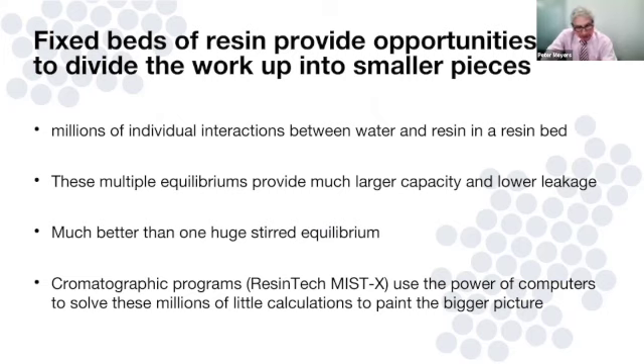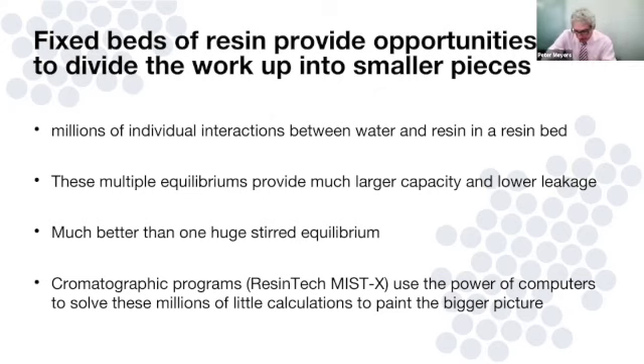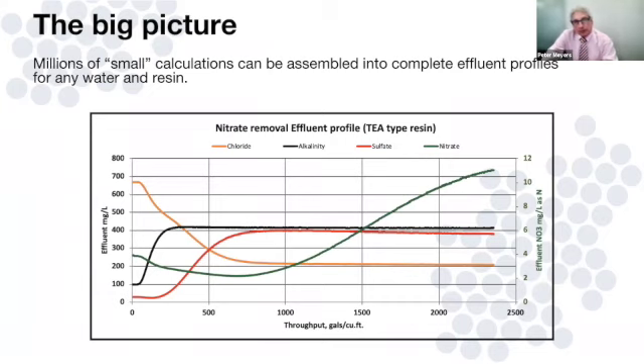There are about 5,000 resin beads in one milliliter of resin, and every one of those beads is interacting with the water separately. By doing millions of individual calculations we can compile a bigger picture that includes higher capacity and lower leakage — much better than a big stirred equilibrium. The same applies in regeneration; you can't regenerate effectively just by mixing resin with chemical. Chromatographic programs like ResinTech MIST-X use the power of computers to solve these calculations.